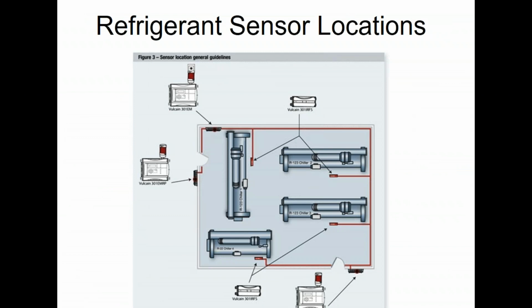We take a typical chiller room, we laid it out here, right? So I have 4 different chillers in here. 3 of them are one refrigerant, 1 is the other. In this case, we chose to put a sensor by every single chiller. We could have, probably this sensor right here, probably could have covered this chiller and that chiller if we really wanted it to, but we put one by each just because. It's not that big of a cost difference in the grand scheme of things.